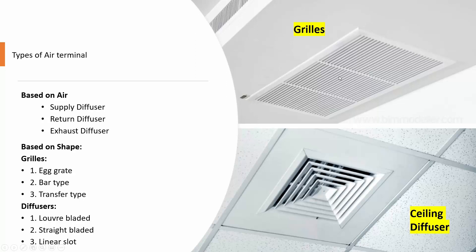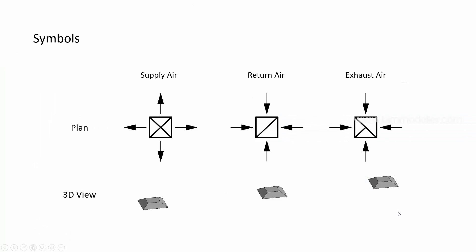The image on the top is a grill, and on the bottom you see a ceiling diffuser. In every design drawing we have symbols. For air terminals placed on the floor plan, we have specific symbols. The arrow indicates the airflow direction — for supply, it goes outside; for return, it goes inside; for exhaust, it also goes inside.